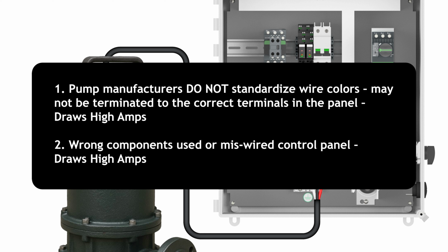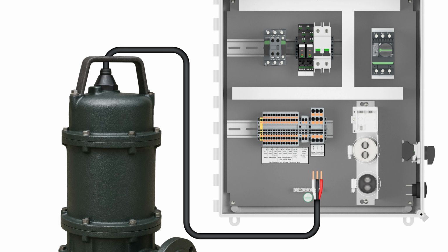If the pump wires are not connected to the proper terminals in the control panel, or if the capacitor kits are miswired or have the wrong capacitor kit components, the pump will draw significantly high amperage that damages both the pump and the control panel. Unfortunately, it is sometimes human nature to ignore the high amperage and just reset the overloads or reset the circuit breaker in hopes the problem goes away. If we understand these pitfalls and we learn how to properly perform a pump system startup, then we can eliminate costly repairs and downtime. Follow these steps for a successful single-phase 3-wire grinder pump system startup.